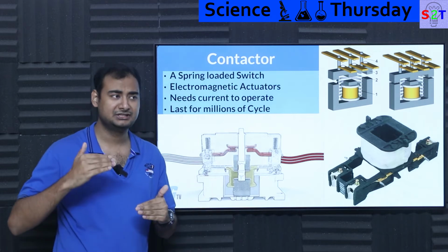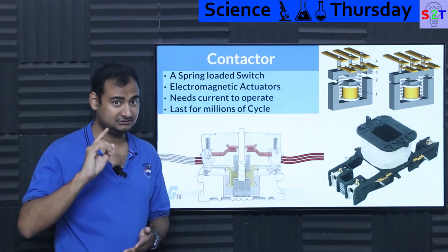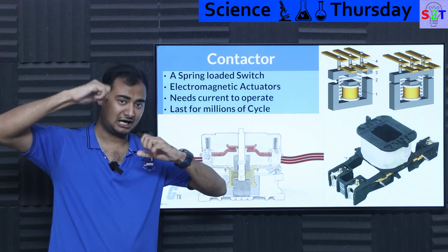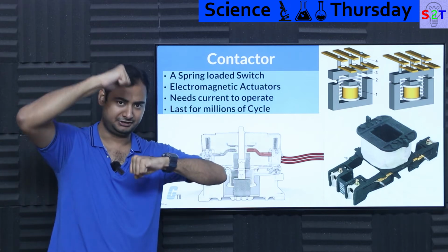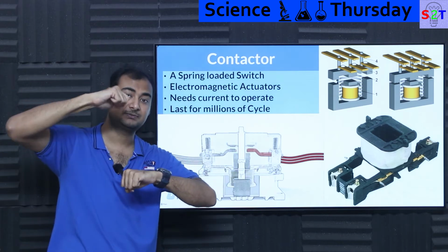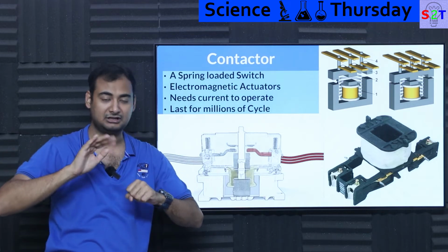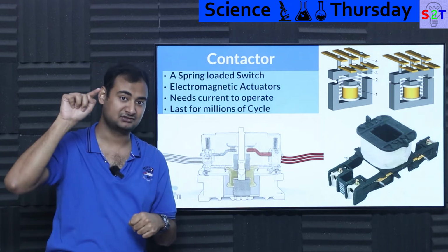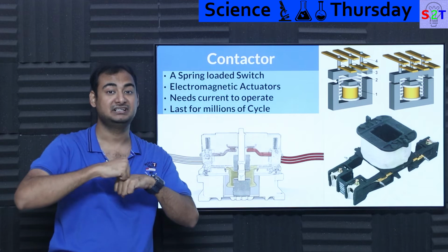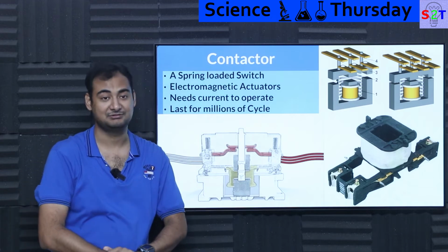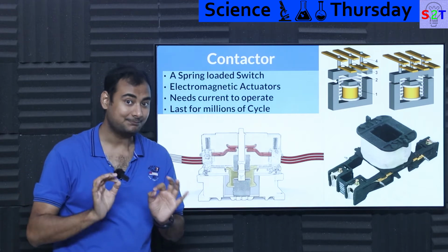For example, the spring, you may think, let's put a very strong spring. You have a backfire problem, because if you have very hard metal, going super hard, going twing, it will bounce. Now the moment it bounces back, it will create an arc, and God help you if that arc happens in an AC waveform when it's going peakwards, it will literally melt it shut. It has happened to enough people that they shall use properly balanced springs.